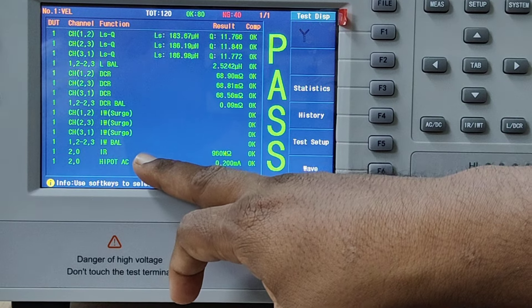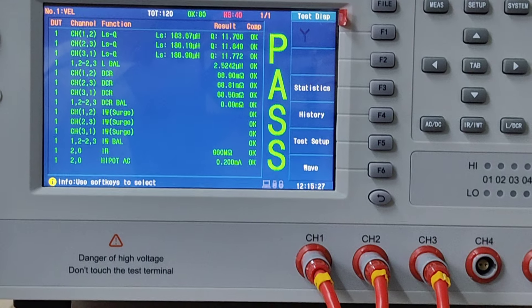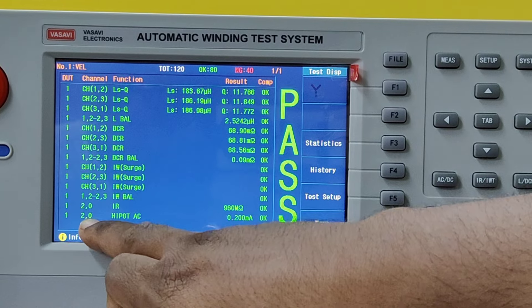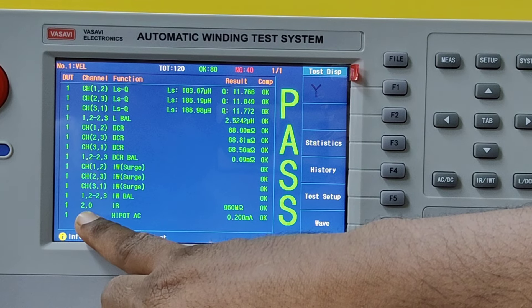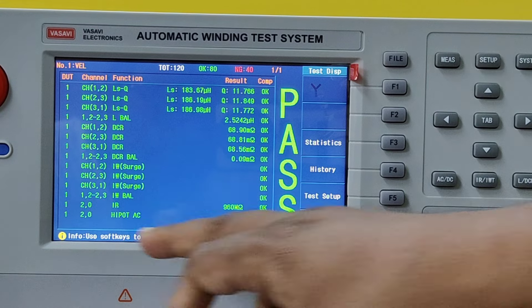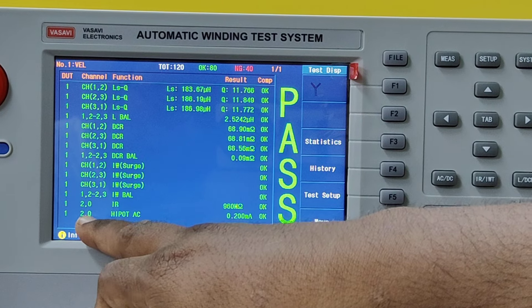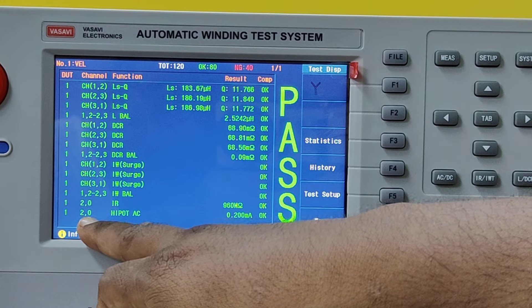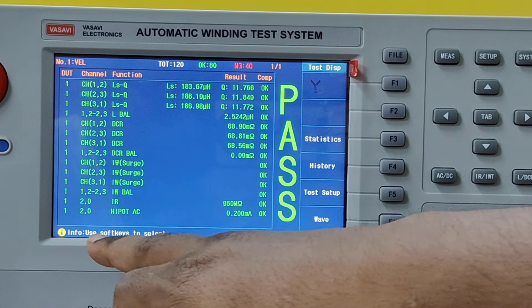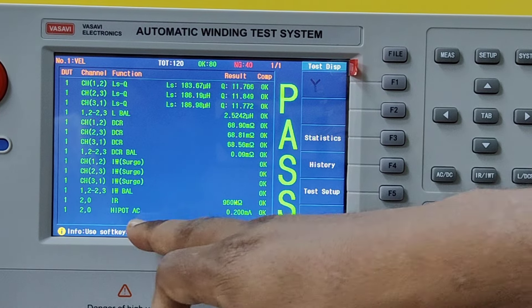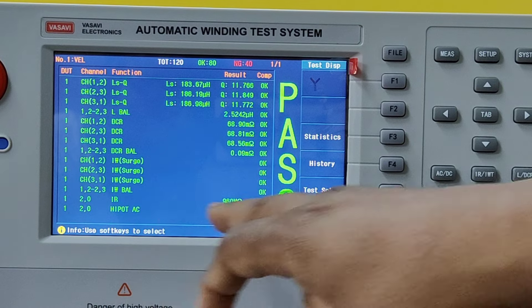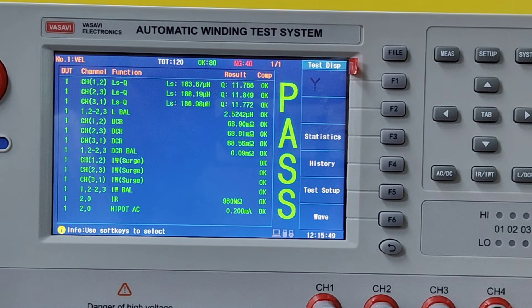Here is the IR result. IR was checked only for the second channel. You can see 2.0 — O stands for return wire, that is ground — the black wire. Between channel 2 and the black wire, IR is passed. Now HV AC, second channel and body — it is within limit and passed.